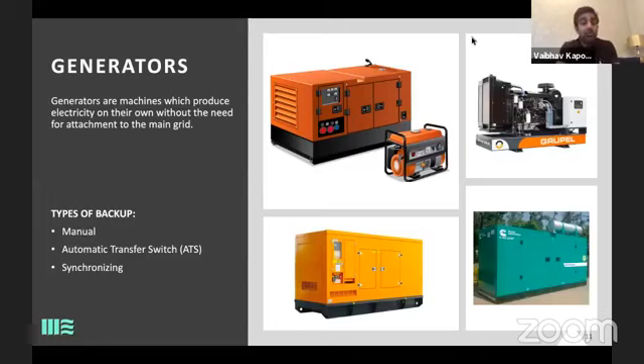We come to the types of backups. Everybody is aware of manual backups, automatic transfer switch, and synchronization. Manual, I'll just briefly go through. In a manual changeover, what happens? Your one genset is running on load, the other genset is running idle, which we call a hot backup. If something goes wrong with the main generator, the hot backup takes over from the main genset. In manual changeover, you need human involvement to do so. You need to pass on a message to your genset operator that something has gone wrong. And if he's present on site, at the genset, then he will do the manual changeover immediately. It will take anywhere from 15 seconds to about 1 minute.